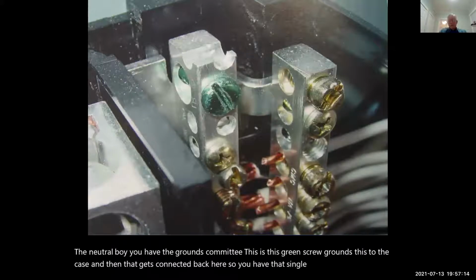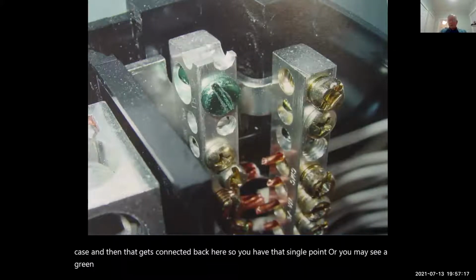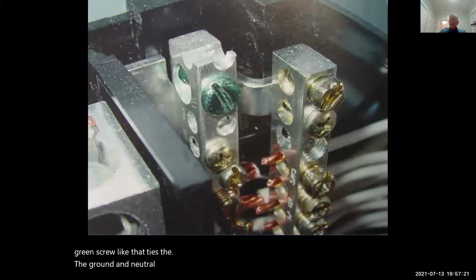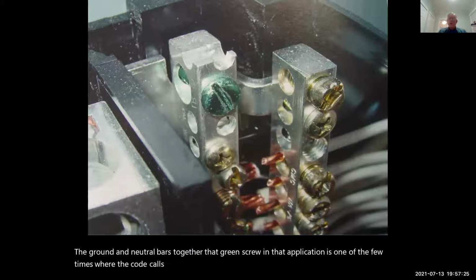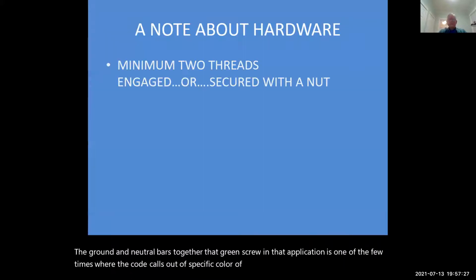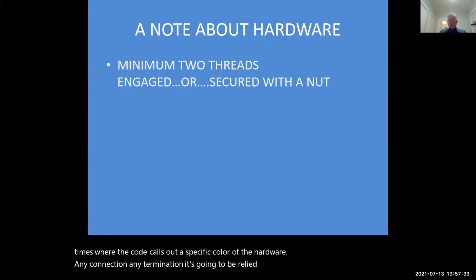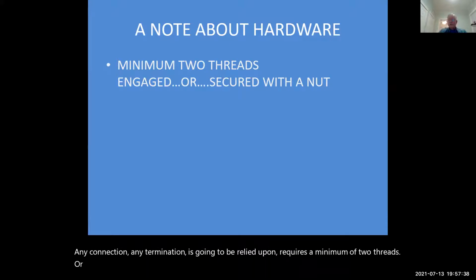Or you may see a green screw like that ties the ground and the neutral bars together. That green screw in that application is one of the few times where the code calls out a specific color of the hardware. Any connection, any termination that's going to be relied upon requires a minimum of 2 threads engaged, or secured with a nut that engages 2 threads or more.